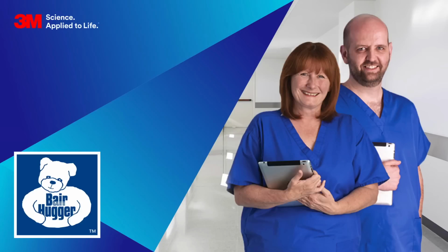So Danny, regarding patient height using the model 545, what is the maximum patient height that can be placed on the adult underbody blanket? As long as the patient's head is positioned on the non-inflated section at the top end of the blanket, allowing the blanket to inflate and allow the flow to go around the blanket, if you've got a taller patient, what you could do is allow the feet just to be off the end of the blanket at the bottom, so there's no upper height for patients. Just on the other paediatric one, they give a specific height. Okay.